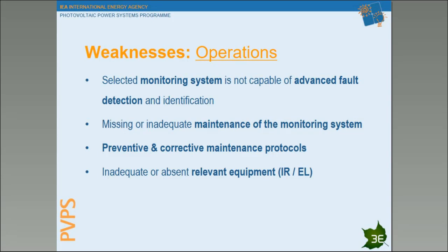We also saw some deficiencies in some cases, but not in many, about the preventive and corrective maintenance protocols. And again, during the operational phase, we also see inadequate or even sometimes absent relevant equipment like infrared or electroluminescence devices.